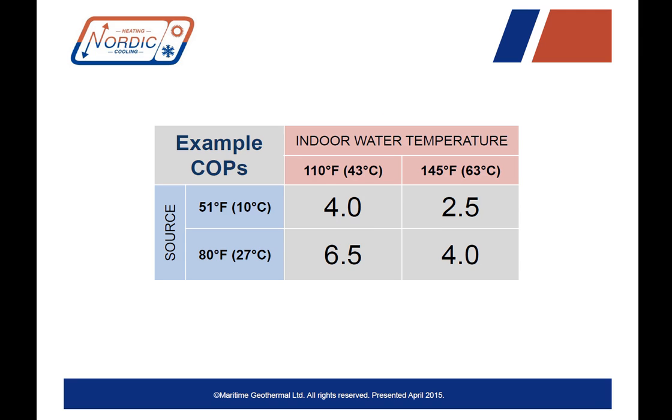What about the COP? The COPs vary a little bit by model size, but in general, using the minimum 50 or 51 degree Fahrenheit source and heating water to 110 degrees Fahrenheit, the COP is around 4. Using that same minimum source temperature and heating water to 145 degrees Fahrenheit, the COP goes down to about 2.5 due to the large amount of temperature lift. If you increase the source temperature to 80 degrees Fahrenheit, you can bump these COPs up to 6.5 and 4 — very attractive COPs depending on your application.